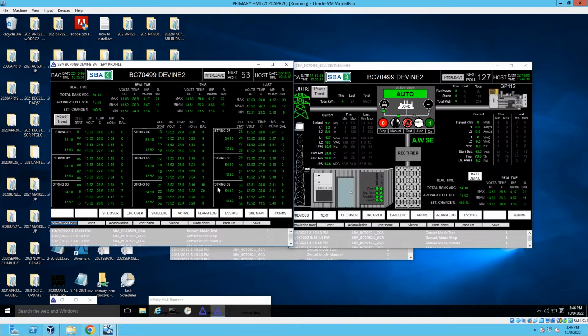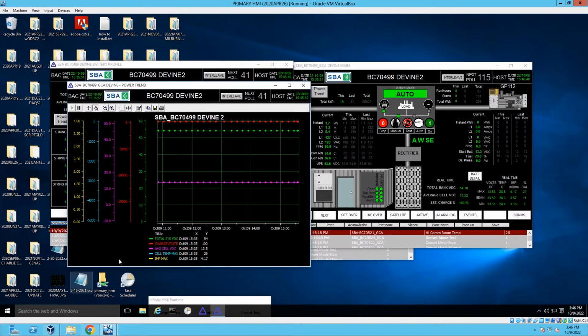Without our unique balancing technology, this would cause cells to charge and discharge at uneven rates, which would promote premature failure of some cells, resulting in an untimely reduction in capacity or potentially a catastrophic failure. At a glance, we can compare extreme values for today versus yesterday. We also have access to trending to view historical data to identify points in time where changes may have occurred.